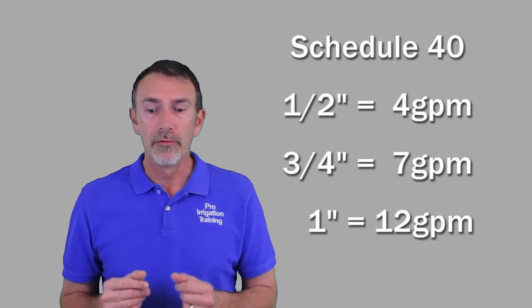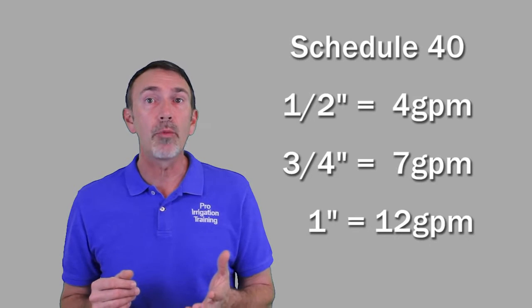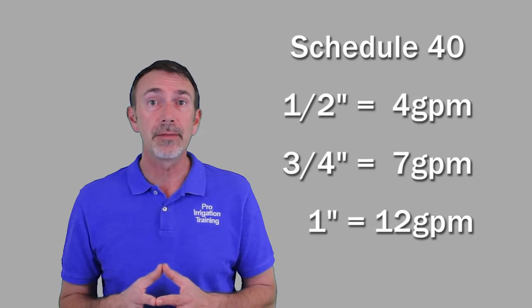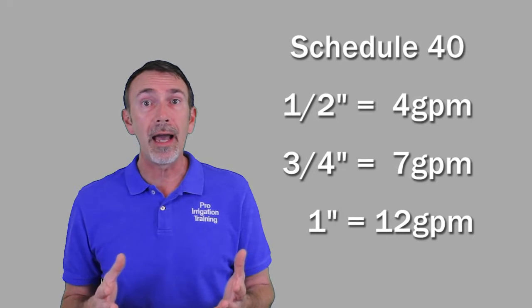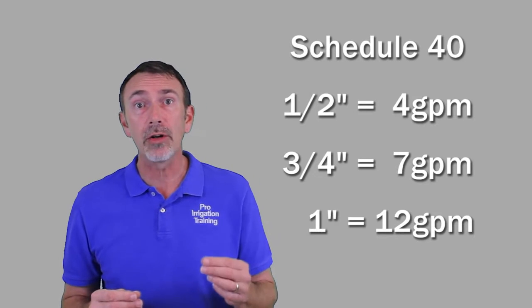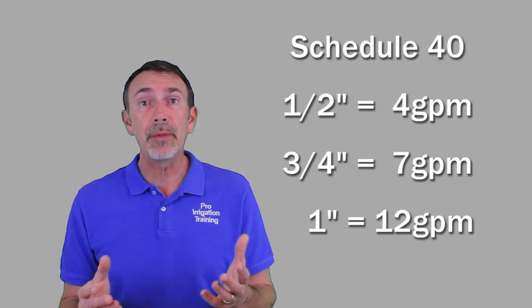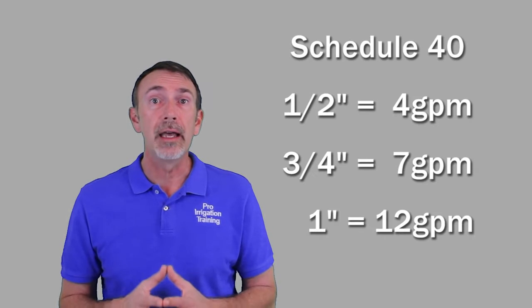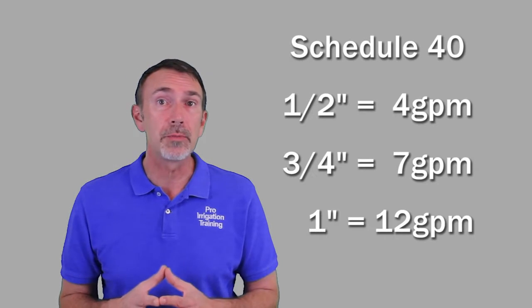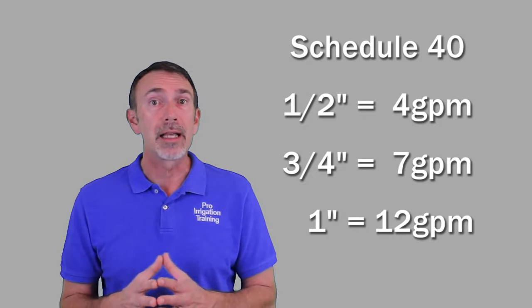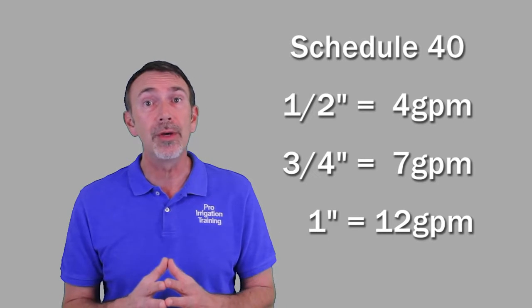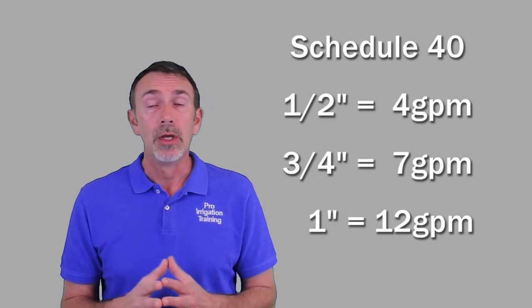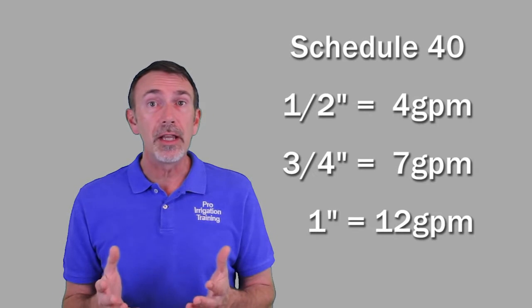Now let's talk about Schedule 40 and go through the fill-ins on the schedule 40. For one half inch pipe, we're going to have four gallons per minute as our limit. For three quarter inch pipe, seven gallons per minute. And then one inch pipe is going to give us a maximum flow rate of 12 gallons per minute safely. Like I said, we can get more than that through these pipes, but you do it at the expense of pressure. So those are the fill-ins, and let's talk about the different ways that we can cut PVC and deal with it.